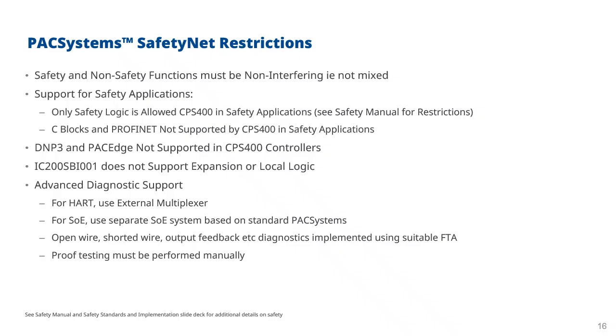Just because PACSystems SafetyNet can do something, it might be that that's outlawed or restricted because it's a non-safe application in the overall safety function. So for example, there might be proof tests that have to be performed at particular times. That would have to be implemented as a manual standard operating procedure. It's not something that the system itself can perform. So you often have these other safety functions and safety things going on around the safety system itself.